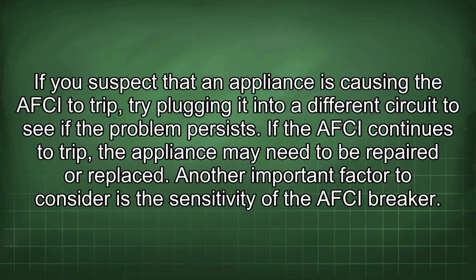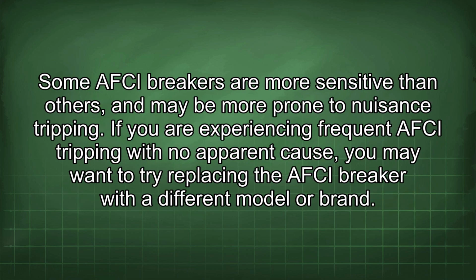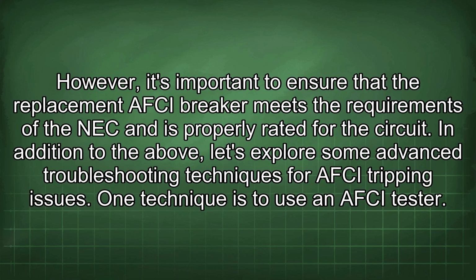Another important factor to consider is the sensitivity of the AFCI breaker. Some AFCI breakers are more sensitive than others and may be more prone to nuisance tripping. If you are experiencing frequent AFCI tripping with no apparent cause, you may want to try replacing the AFCI breaker with a different model or brand. However, it's important to ensure that the replacement AFCI breaker meets the requirements of the NEC and is properly rated for the circuit. In addition to the above, let's explore some advanced troubleshooting techniques for AFCI tripping issues.